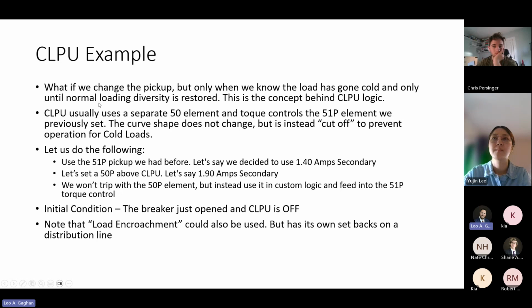We'll run into an example here. So one of the solutions, what if we change the pickup, but only when we know we have cold load, and only until normal loading diversity is restored. This concept is referred to as cold load pickup logic. Cold load pickup logic usually uses a separate 50 element, and torque controls the 51P element we previously set. So the curve and shape do not change, but instead it is cut off to prevent the cold loads.